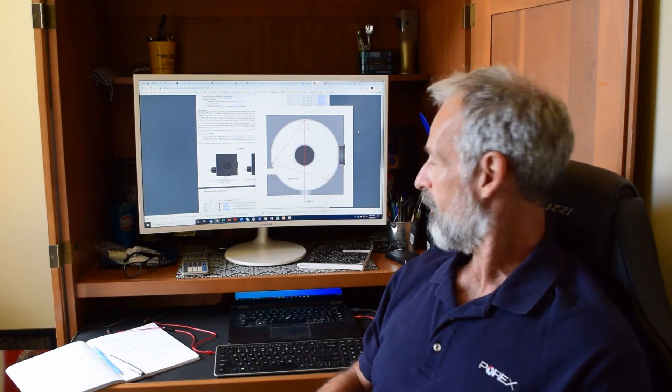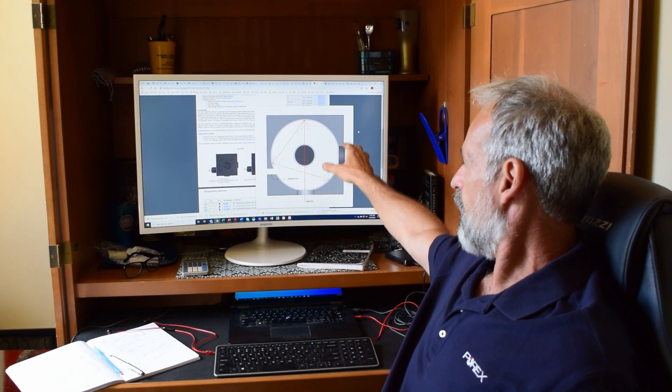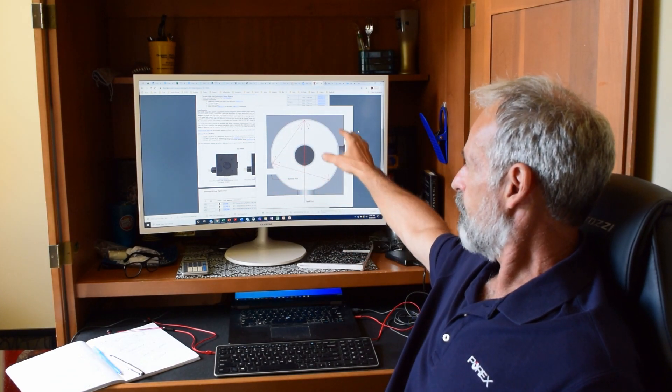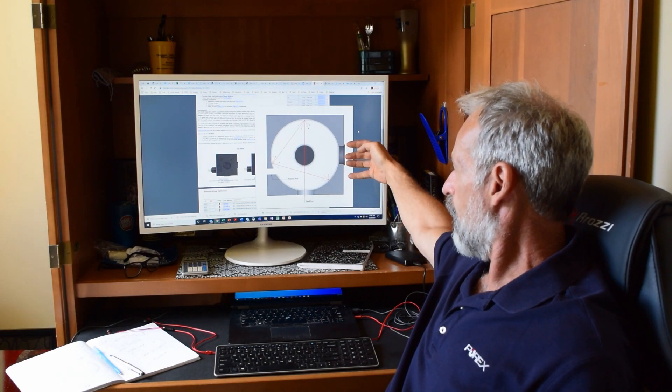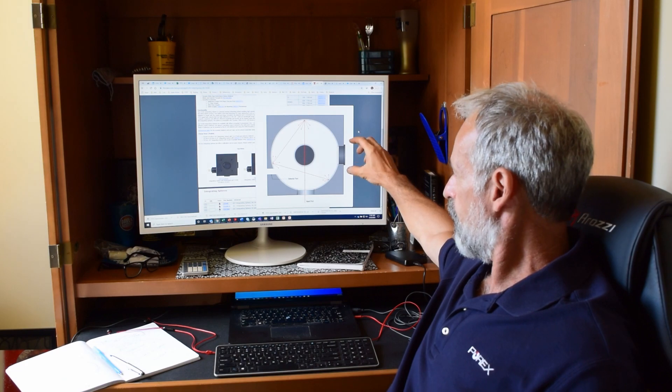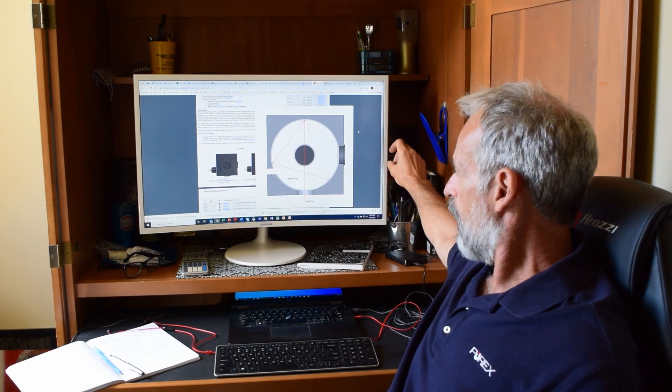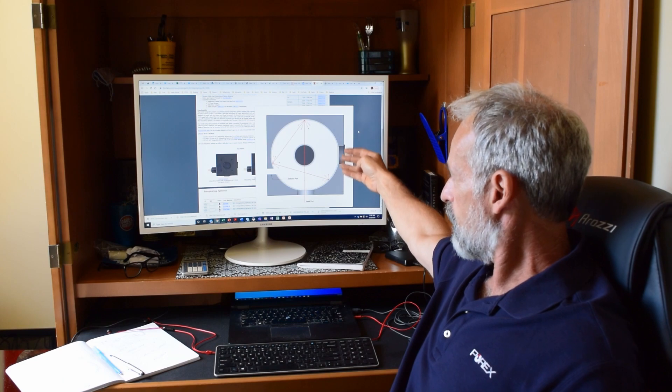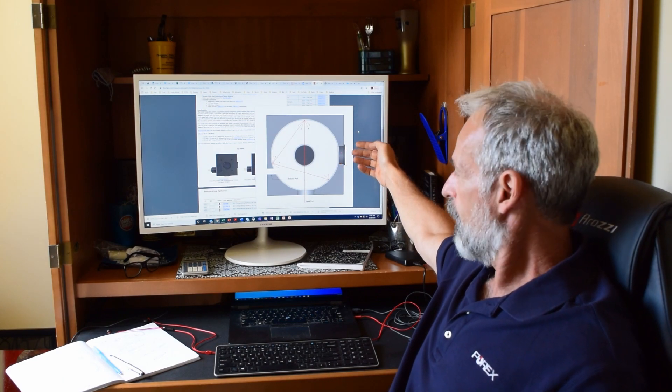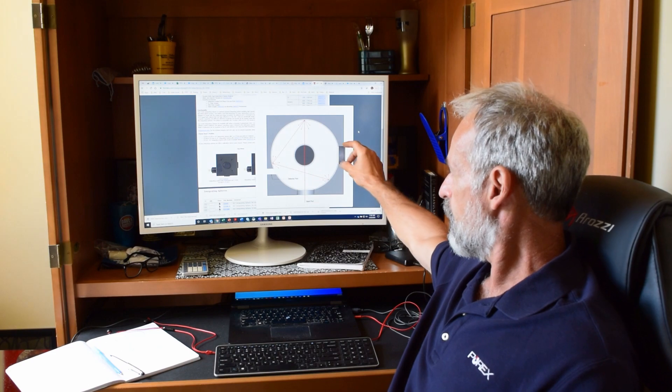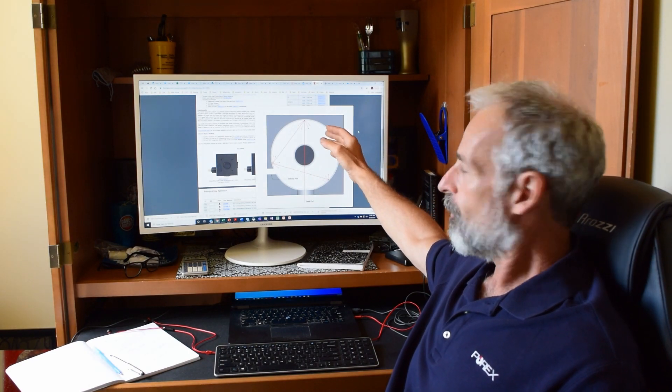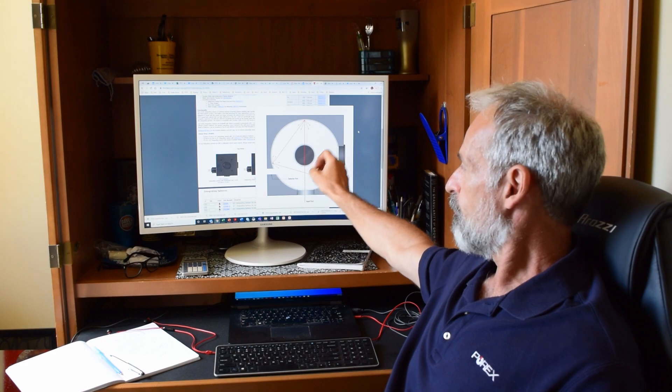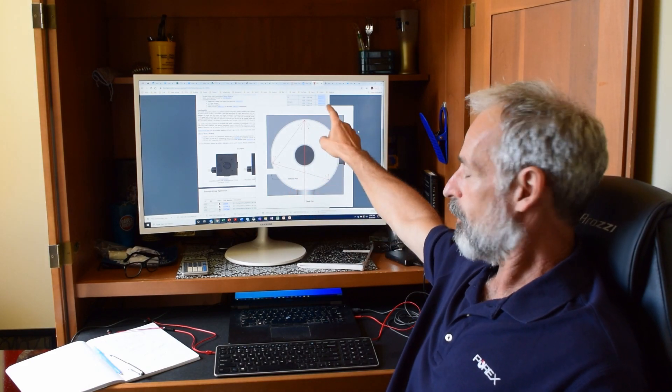An integrating sphere, for those of you who don't know, is a spherical device which is coated in a very highly reflective material. You can put a sample on one side to see how reflective it is. So in other words, if you pull it out, the light comes out; put it in, that surface will become reflective and the detector which is on the other side can detect the difference of having no sample or a standard or whatever else you may have in there versus the incident light which would come into one side.